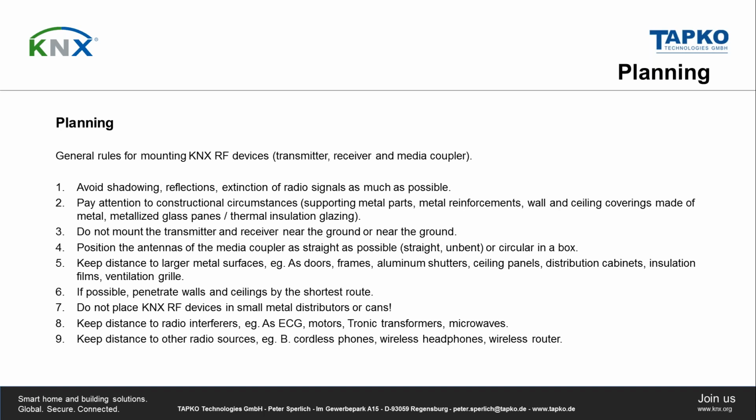The antenna must be really free when you install them. Don't fold the antenna if there's an antenna on the device. And also keep distance to things that could interfere, like engines or transformers or microwaves.